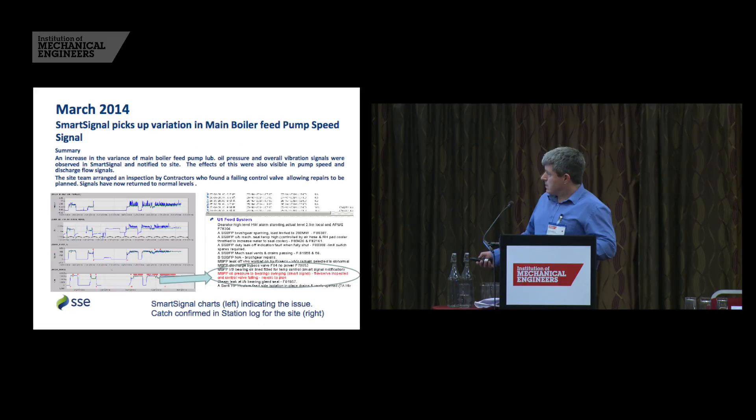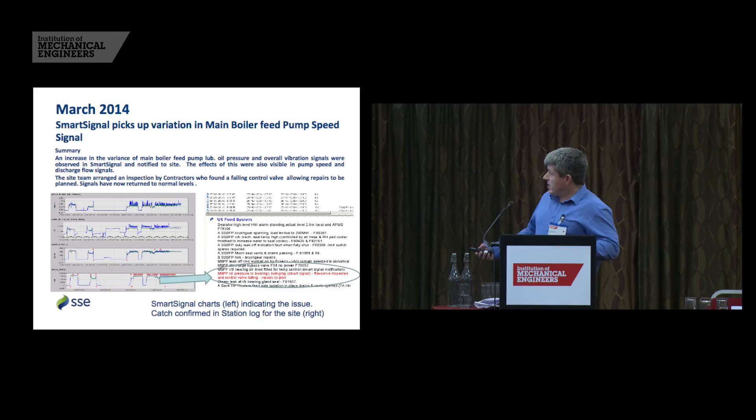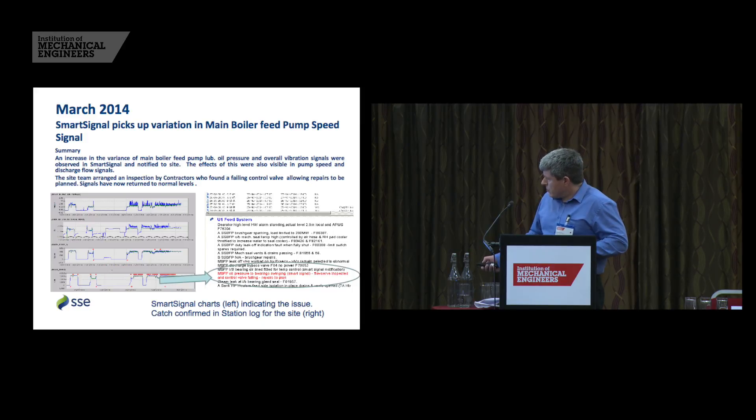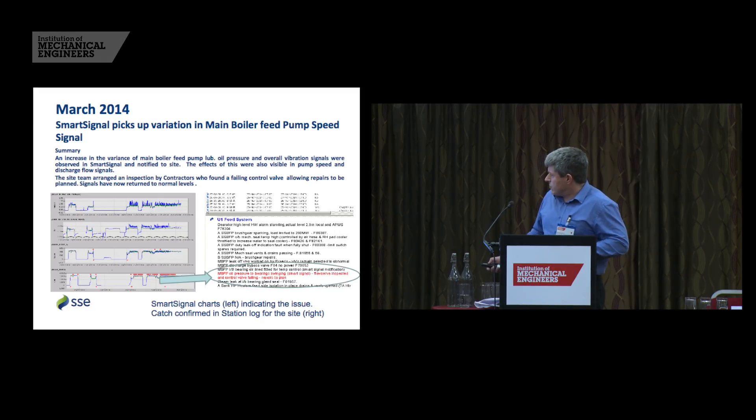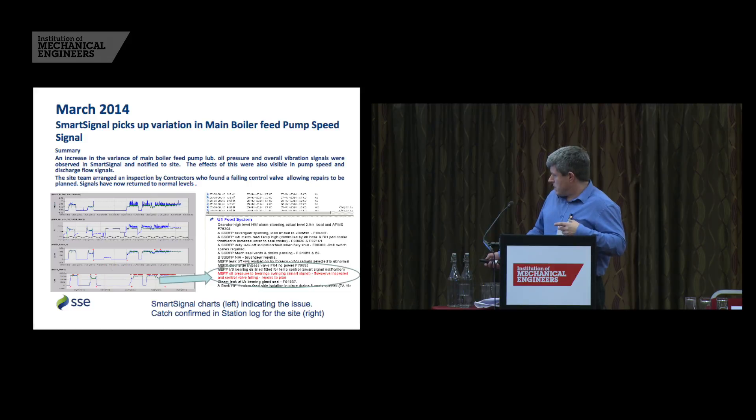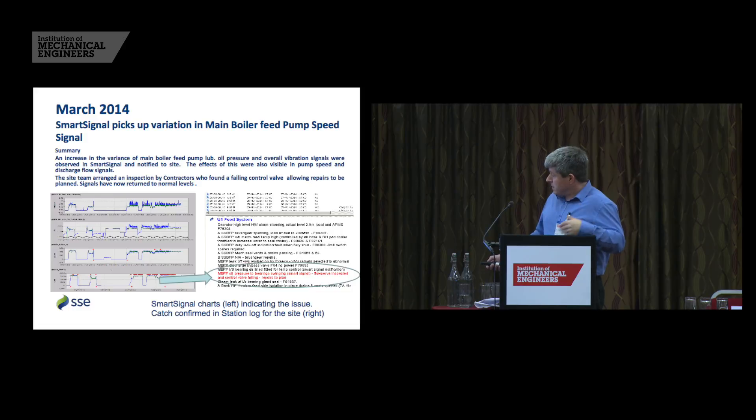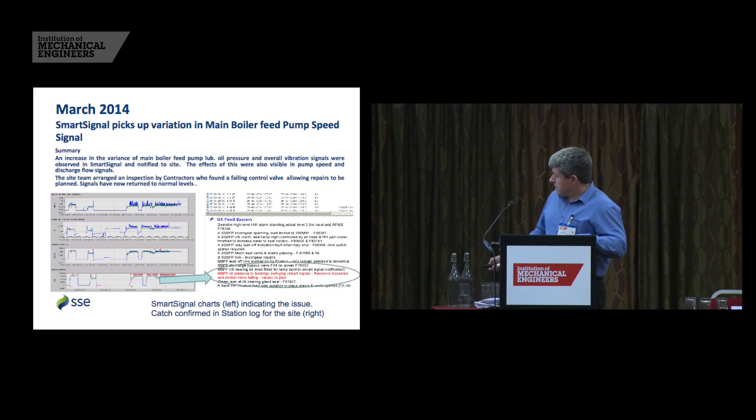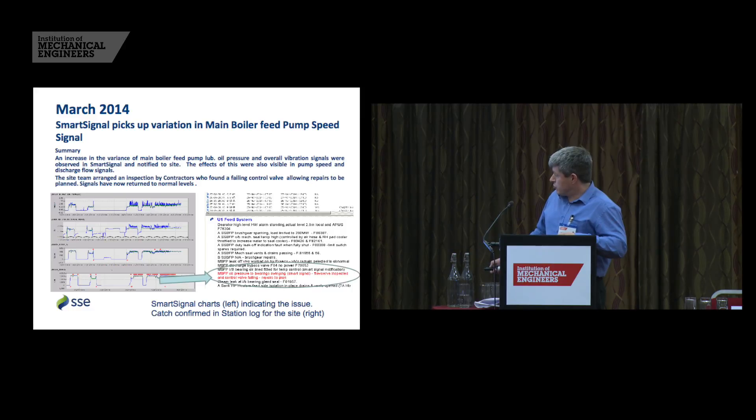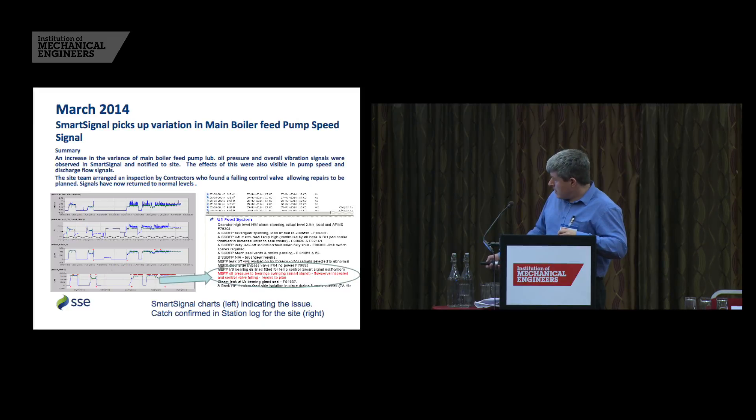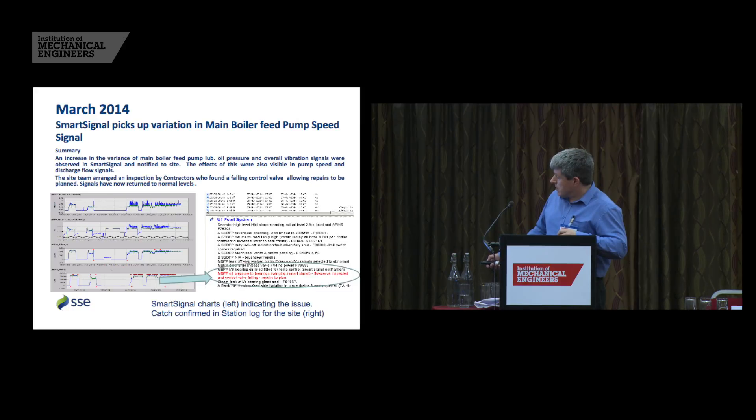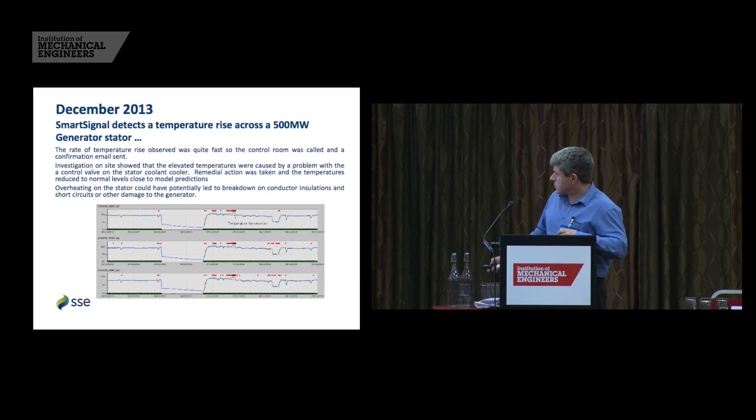Just a couple more quick ones, because I know I'm running short of time. This is on a main boiler feed pump signal. So here we see the speed signal actually was changing and changing quite rapidly. So it was throwing up a large number of incidents here. And when we look at the, I believe that's the oil pressure tag there, we found that one of the control valve had been failing and it had been swinging and operating out of control. So the oil pressure to the bearings was fluctuating. Here we have down here, the report made by the site in the online log book. So we could see where they'd picked up our notification and got into the Flowserve, the contractors looking after that pump and the plan to repair. And you can see here where the repair happens. Then everything goes back to normal again after that. So this is the smart signal incident and there's a period of time to plan a repair. And that was done. It looks like without even bringing the machine offline.